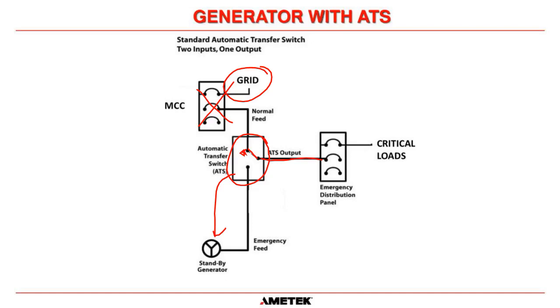So you are going to lose power at this point here at your critical load panel for about 30 seconds to a minute while the standby generator runs up to speed. And then once it does run up to speed, it sends a signal to the automatic transfer switch and closes this. So this will now be open, and it will close the switch here, and the emergency generator will feed the critical loads. Now, obviously, the biggest downfall of this is you are going to lose power for about 30 seconds.